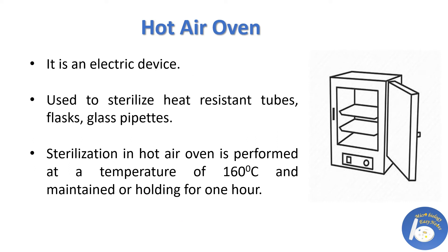Another dry heat sterilization method is the use of a hot air oven. It is an electrical device that utilizes dry heat to sterilize various types of equipment and articles like glassware, surgical equipment, metals, and powders. It provides a continuous flow of heat through blowers and heaters which kill microorganisms present on the surface of the objects.